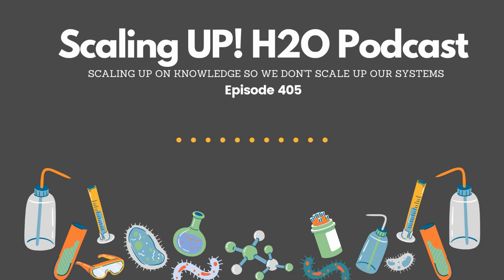How did you balance those two things, the excess solids and them wanting to get higher cycles? In this case, one of the things we needed to fix first was the use of chlorine gas that they were using. Chlorine gas is a very effective biocide, but it carries some risk in management and also creates challenges with pH, especially at a refinery with a lot of hydrocarbon contamination.